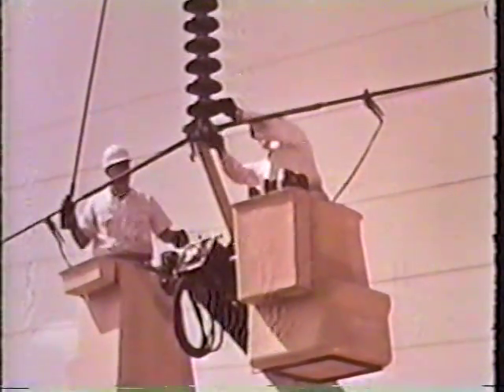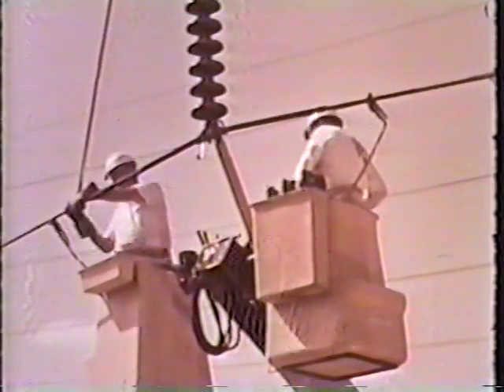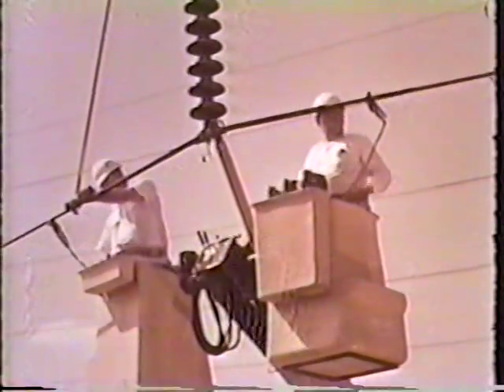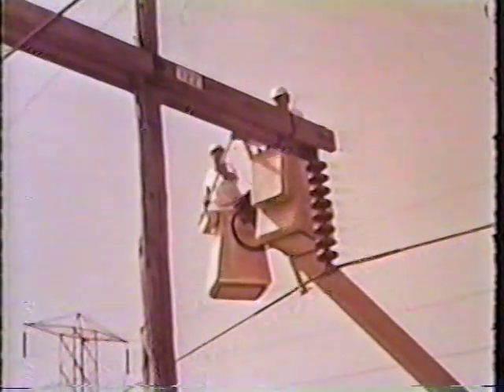On a job such as this, for example, a trained bare-hand crew will average less than half an hour from the time of leaving ground until return. With conventional hotline methods, the job would average about 1.5 hours, a ratio of 3 to 1 in favor of the bare-hand method.